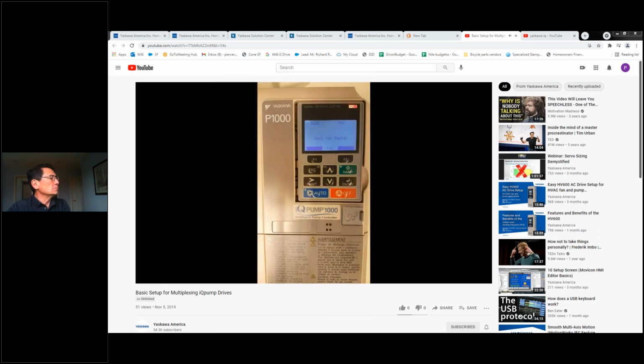The last parameter is P925, which sets how many drives are communicating on the network. With the 01 flashing, press Escape once to get the 1 flashing. Change the 1 to a 9 and press Enter. Change the 01 to a 25 and press Enter.